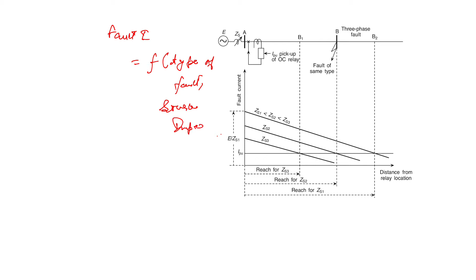This is clear from these two diagrams. These are actually variable, and keep on changing. So we must look for a relay whose reach does not depend upon the actual magnitude of the fault current, and the search for this relay leads to the type of relay known as the distance relay, which does not depend upon the actual magnitude of the fault current, but on the ratio of the voltage at the relay location and the fault current.